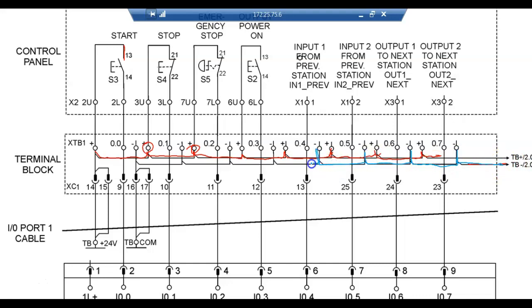And this comes up to a terminal board. So there's mine, so notice we're running sourcing inputs on our PLC. That means all our push buttons and stuff has got to hook up to the positive. So notice here's this push button right here, here's the start button. It's hooked up to the positive, and then the other side comes down, it's going to go to 0.0.